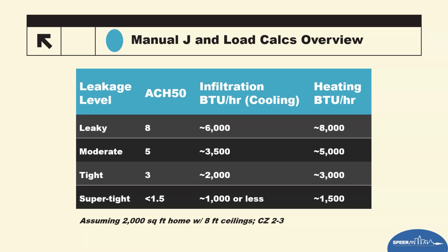But here we see an example, looking at the difference in leakage. Again, this is being assumed when building the model. We can put super tight, we can put tight, we can put moderate, we can put leaky. If an HVAC guy always picks leaky because that's the way he does it, and it sells bigger equipment, and the building that is actually being constructed is going to be tight, that is off in sizing. That's a complete disconnect from reality of what's happening. So we need to actually have the right data.